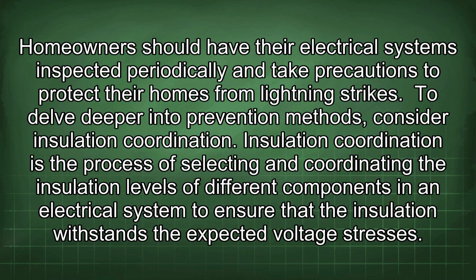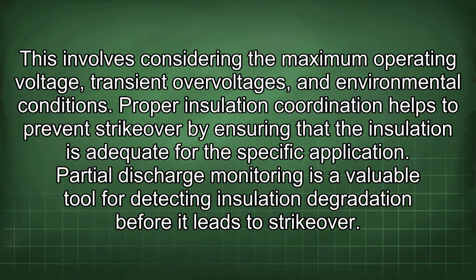ensure that the insulation withstands the expected voltage stresses. This involves considering the maximum operating voltage, transient overvoltages, and environmental conditions. Proper insulation coordination helps to prevent strikeover by ensuring that the insulation is adequate for the specific application. Partial discharge monitoring is a valuable tool for detecting insulation degradation before it leads to strikeover.